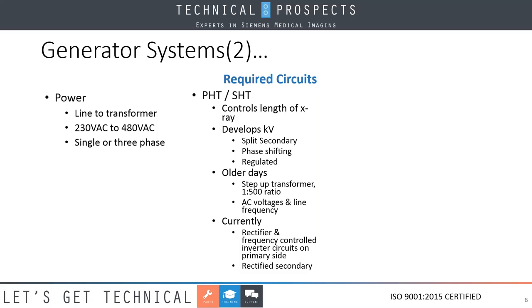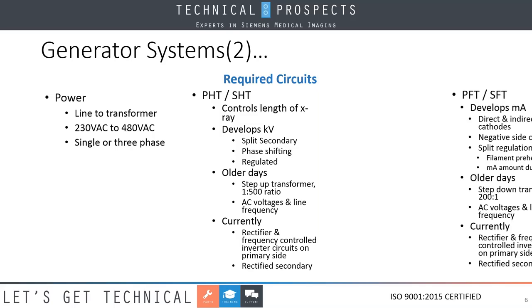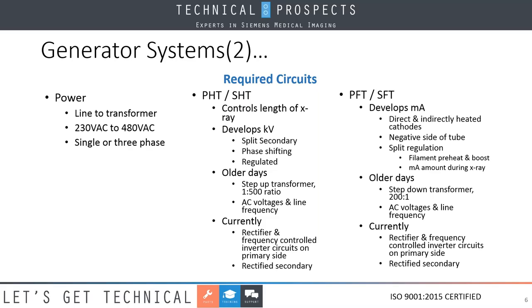Somewhere in the late 70s, one of the manufacturers changed everything. And currently, we now use rectifier and frequency controlled inverter circuits on the primary side, but we still rectify the secondary. So we've looked at three of our five circuits. The last two circuits are the primary filament and the secondary filament.